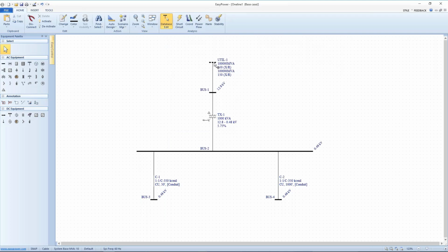And then by default, it's going to plot the TCC curves when we get to coordination, and this is per ANSI standard C57.109. They said, Jim, I've talked to the utility, and I've got the data from them. They supply an available short circuit current of 45,000 amps. I take that back, 55,000 amps. The X over R is 7.6. They didn't give me the short circuit current for the single line to ground, so I'm going to use the same numbers because that's a more conservative approach.